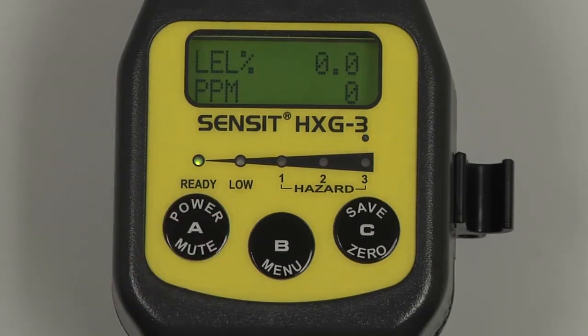To perform a flow check, place a finger over the inlet at the end of the gooseneck until a flow block message appears. Allow the instrument to warm up for an additional 5 to 10 minutes before calibrating.